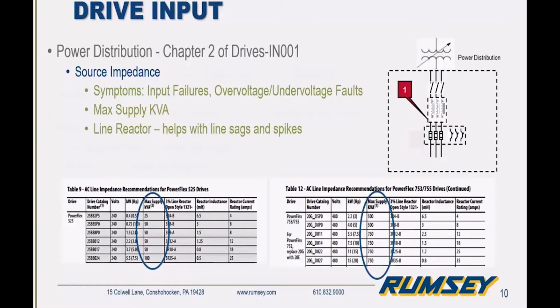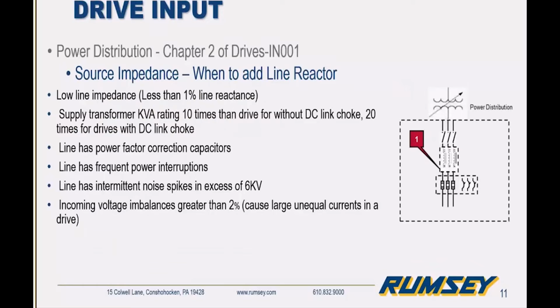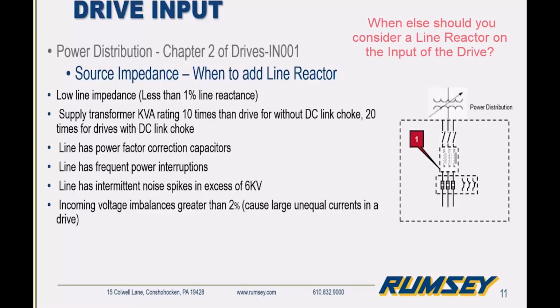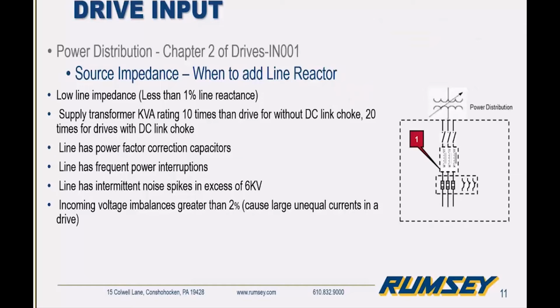So in addition to the source impedance, or looking at the kVA tables as a reference, there may be other circumstances where it might be a good idea to have a line reactor out there on the input of the drive. This lists some examples, just a few of them here. Power factor correction capacitors, if they're in the system, you're aware of them, might be necessary to add a reactor there. Also, if you have and know of a voltage imbalance you're going to be installing the drive in, be another good example.